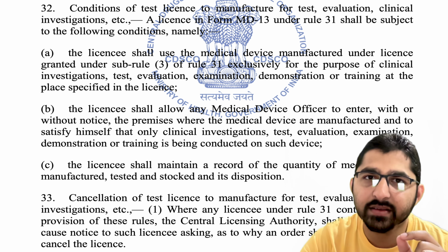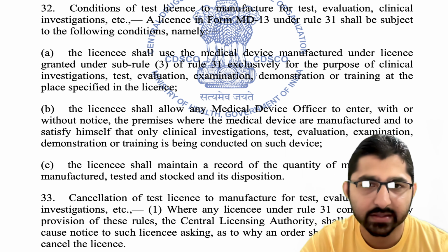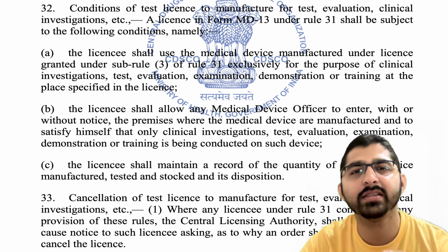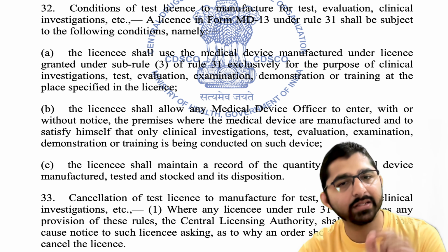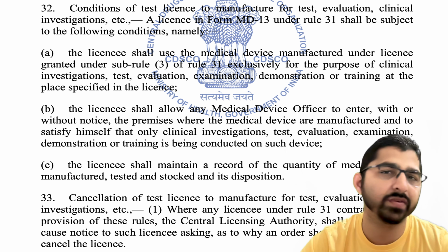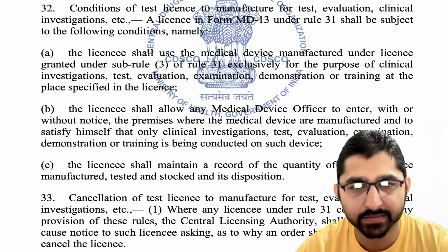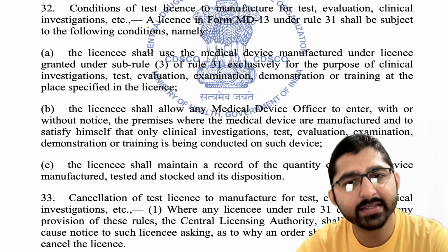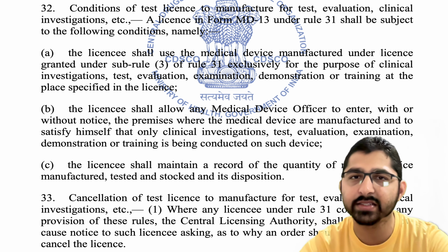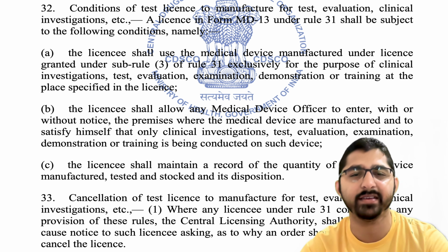The licensee will allow any medical device officer to enter, with or without notice, the premises where the medical devices are manufactured, to satisfy himself that only the clinical investigation, test, evaluation, examination is being performed under the test license. So these batches will not be used for commercial purposes. When I say commercial purpose, you can't sell these test batches in your market. The licensee shall maintain the record of the quantity of medical devices manufactured, tested and stocked, and their disposition. So for each and everything, a proper reconciliation should be there.